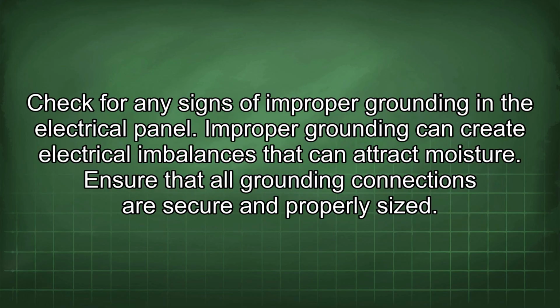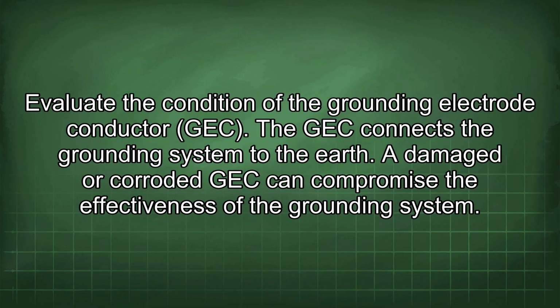Check for any signs of improper grounding in the electrical panel. Improper grounding can create electrical imbalances that can attract moisture. Ensure that all grounding connections are secure and properly sized. Evaluate the condition of the grounding electrode conductor, GEC. The GEC connects the grounding system to the earth. A damaged or corroded GEC can compromise the effectiveness of the grounding system.